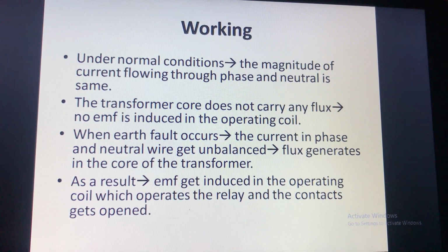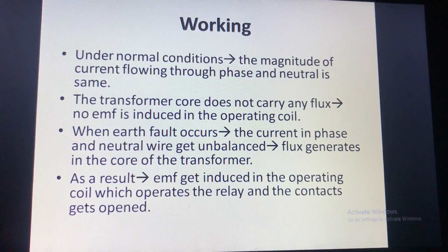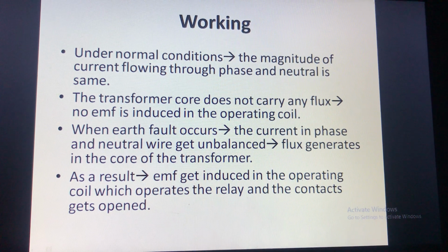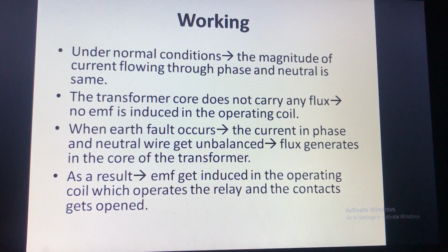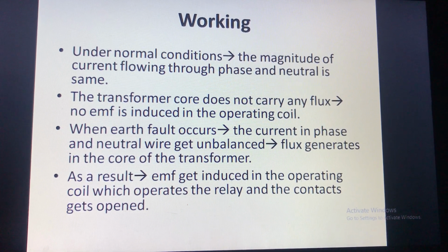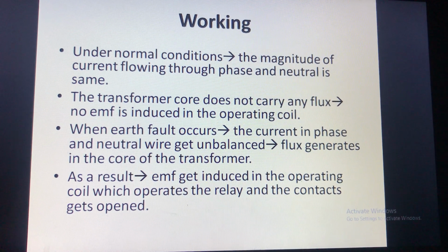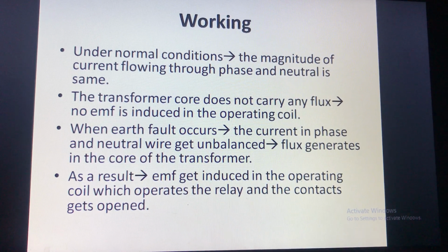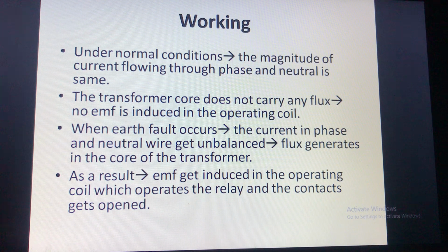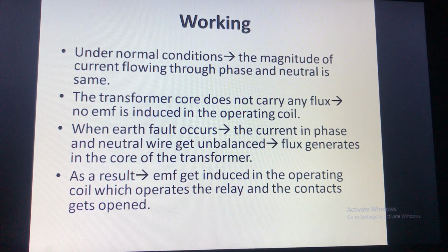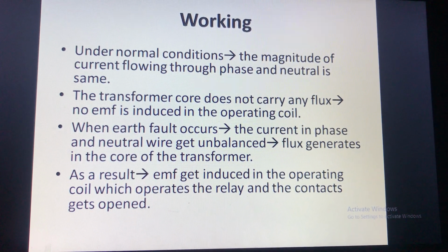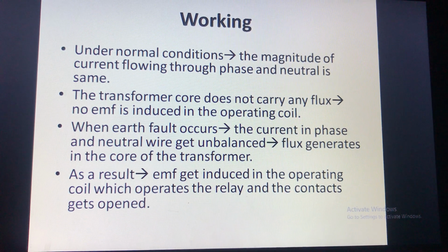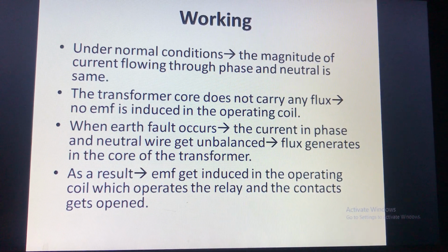So here's the working. Under normal conditions, the magnitude of current flowing through phase and neutral wire is the same because there is only voltage drop in the load. So under normal conditions, the current should be the same in phase and neutral wire. So the transformer core, which carries both these wires, should not carry any flux in this case, and no EMF gets induced in the operating coil.